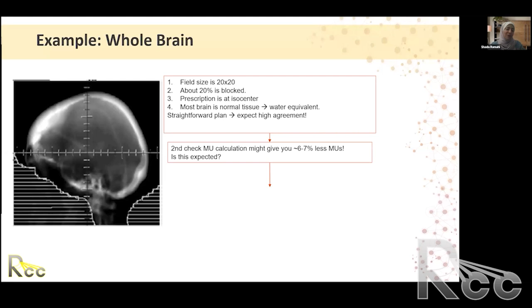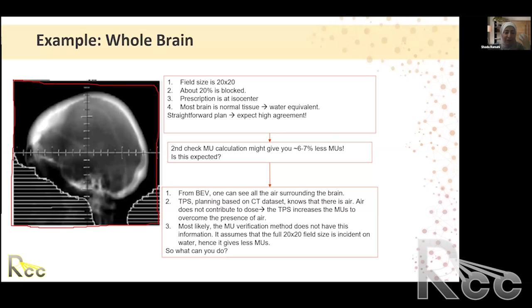When you put in the planning system, or in your manual calculation, field size 20 by 20, and you're looking at the PDD for 20 by 20, remember, how did you measure your PDD? You measure 20 by 20, all of it in water. But in fact, we have air here. Air does not contribute to dose. Air does not contribute to scatter. So not all of your field size is generating scatter, is generating dose.